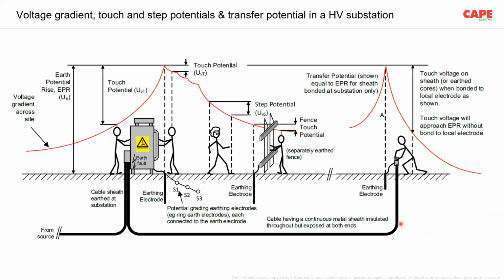Also in the EN 50522, you can find the problems explained, such as the touch voltage, step voltage, and transfer potential. Transfer potential, I just explained here. You see, there is a transformer here. There is an earth electrode plus earth grid. Whenever there is a fault current flow, you see the potential of this particular point is at a very high level. You have a touch voltage problem here. You have a step voltage problem here.